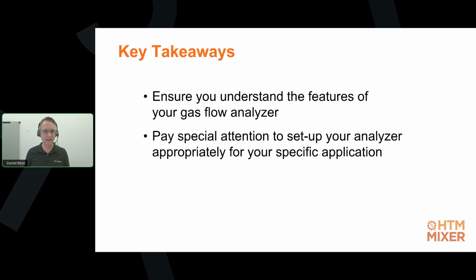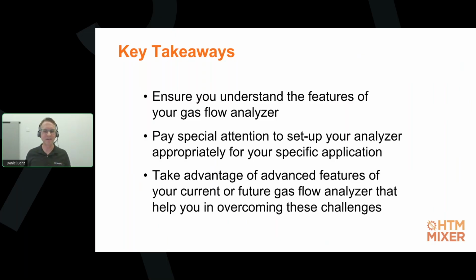If there is one single thing I would like you to remember from this session, it is that your gas flow analyzer needs to be set to the same gas standards used by the ventilator. And last but not least, also take advantage of the advanced features of your current or future gas flow analyzer that can help you reduce the risk of insufficient settings and measurement errors.